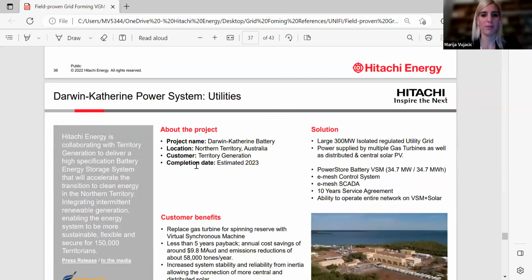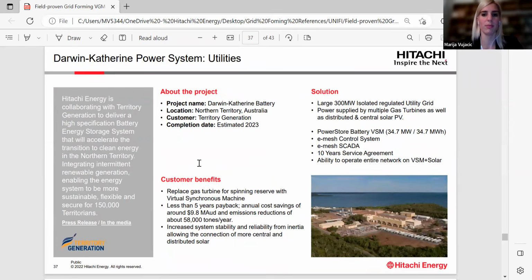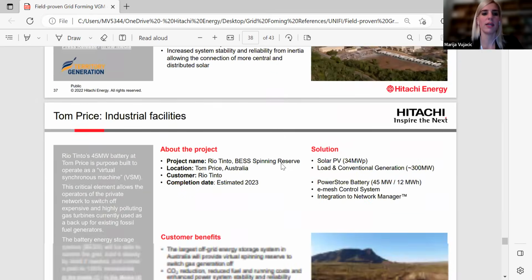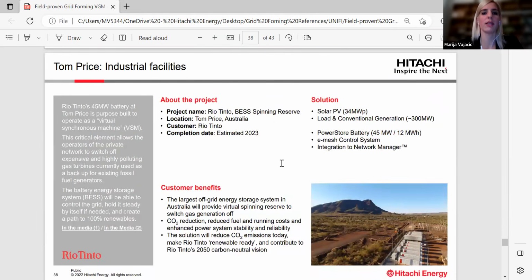Okay, so very briefly, I'd like to mention that we have two big battery energy storage grid forming systems under commissioning now in Australia. One of them targets to replace gas turbines for spinning reserve with VSM, and the control is managed by e-mesh Control System and SCADA. Similar functionalities will be provided also for a Rio Tinto project. Again, quite a high power rating, 45 megawatt, 12 megawatt hours, and we are looking forward to being able to discuss and present results and recordings from these two projects in the next months.